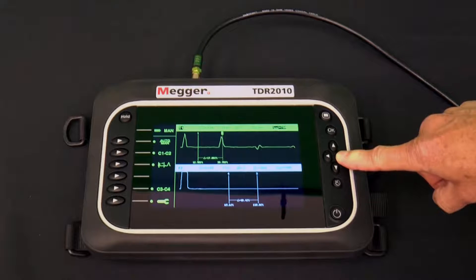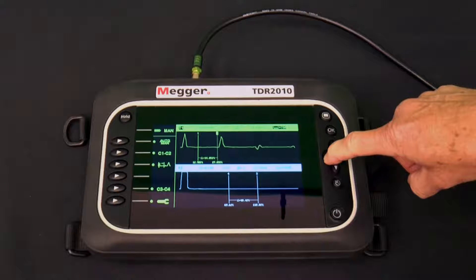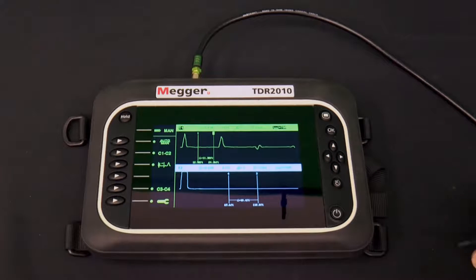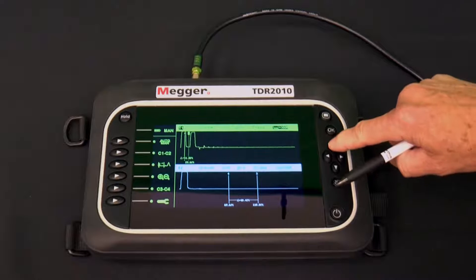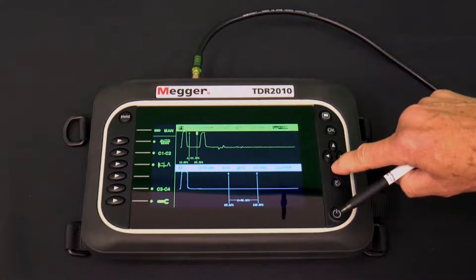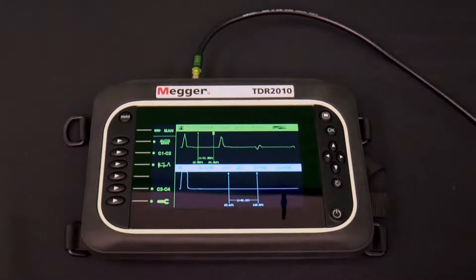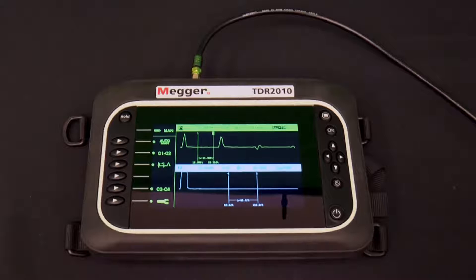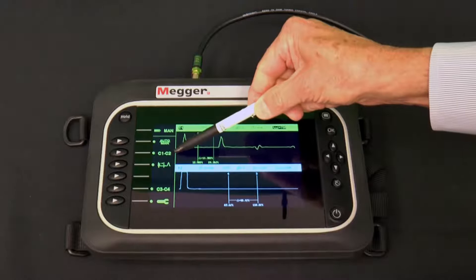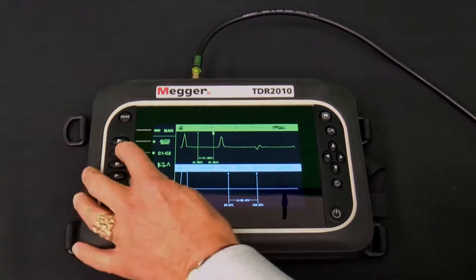The left or right arrow of the navigation group may be bumped or held down to move the active cursor. If it is held down, the speed with which the cursor moves increases the longer it is held down. Using the up and down arrows of the navigation group, increase the amount of cable displayed on the screen for the active trace until an event is visible. The first soft key will alternate between manual and automatic mode. The second soft key with the icon C1, C2 tells the left and right arrows which cursor to move.